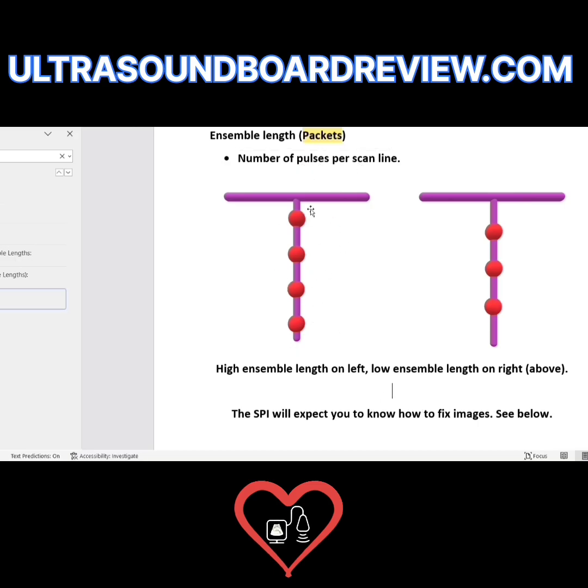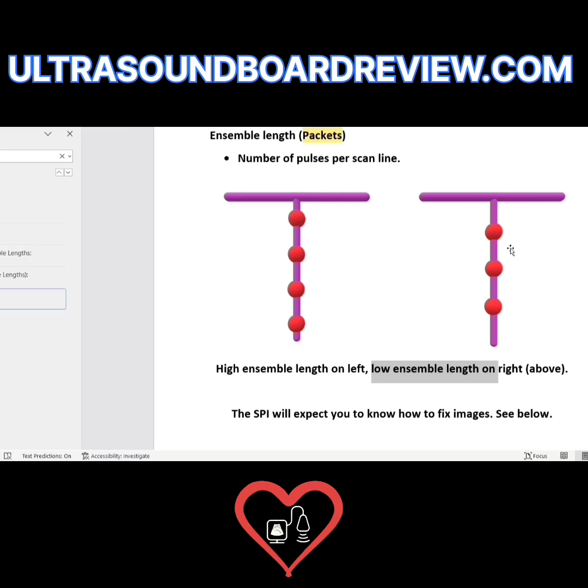The packet size on the left side is high — that's a high ensemble length. The right side is a low ensemble length. The problem with packets is that the more you have per scan line, the more your temporal resolution is reduced.